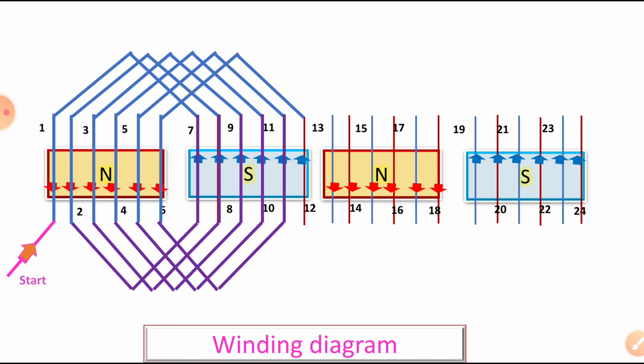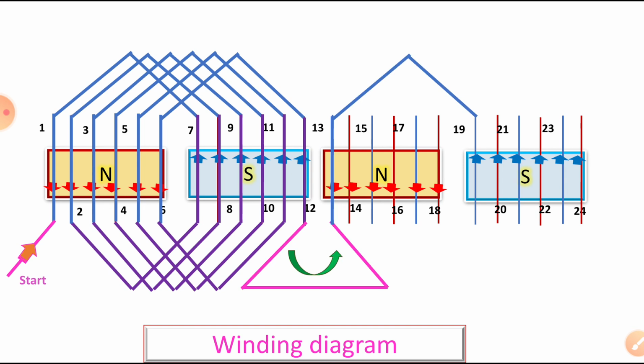So now all these conductors are engaged. Now the 12th conductor has to connect by the front pitch. Here is the testing point. So 12 plus 1 you have to take for another north pole south pole pair. Okay, so now I take 12 plus 1, 13th. I will connect to the 13th here. Just you can see here. So the 13th conductor I connected here.